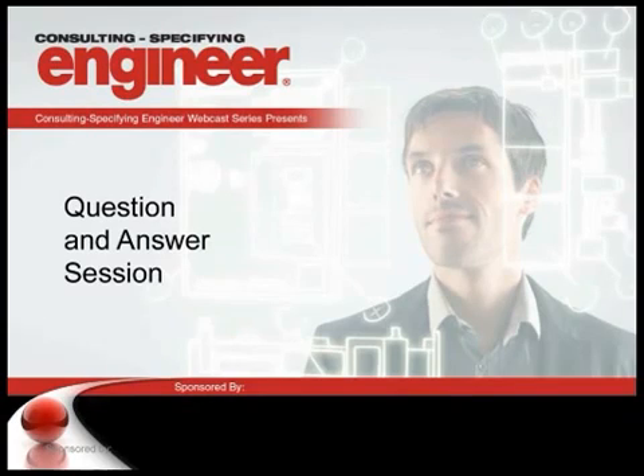Okay. Thank you. Next question is for Jim, and it comes from Joe Saad, Jr. from Greenville, North Carolina, asking, is there instantaneous overlap on the TCC? There is some instantaneous overlap on that TCC. This was in regards to one of our particular slides, where we showed the generator coordination at the end.